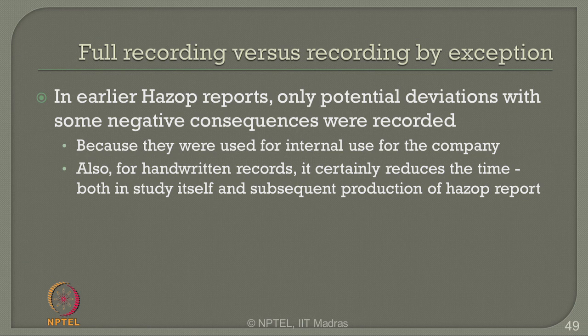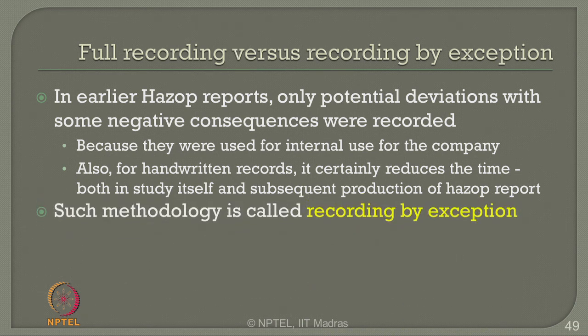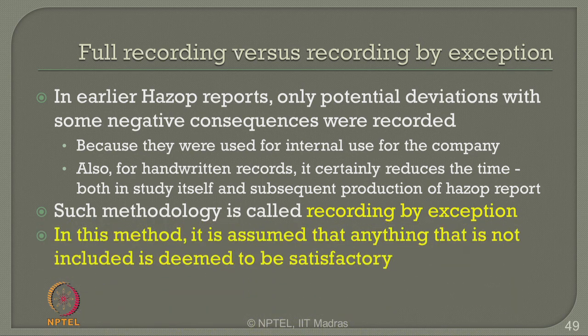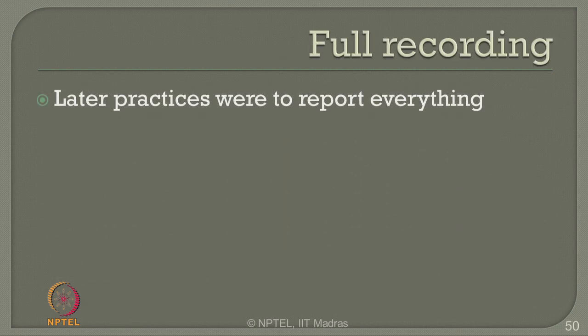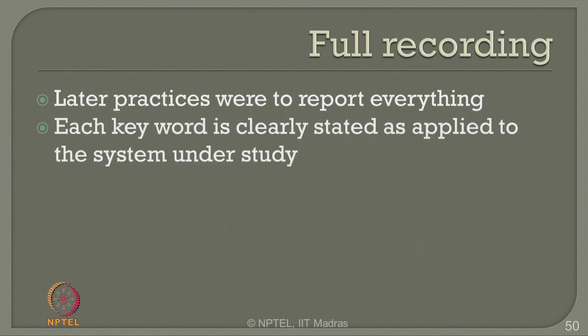Therefore, to reduce the volume of the report and the time in reading the report, only potential deviations were reported. Such methodology was called recording by exception. In this method, it is assumed that anything that is not included is deemed to be satisfactory, whereas in the present scenario people follow full recording. Full recording is followed because nowadays HAZOP reports are purely electronic in nature.